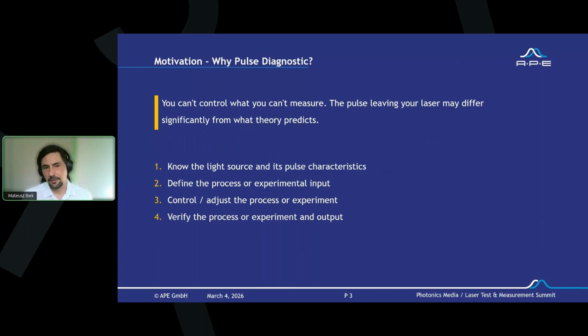Why is it important to have laser diagnostics? You can't control what you can't measure. The pulse leaving your laser may differ significantly from what theory predicts. So there are four logical steps. You have to know your light source and its pulse characteristics. You have to define the process or experiment input. Then you have to control and adjust the process or the experiment, and verify the output. For these steps in between, there are diagnostics or measurement devices that allow you to control and adjust the process and verify it.